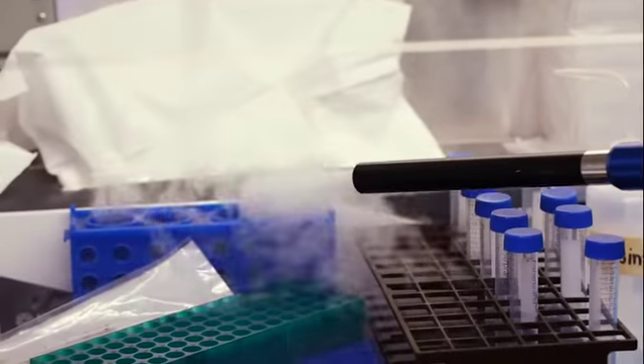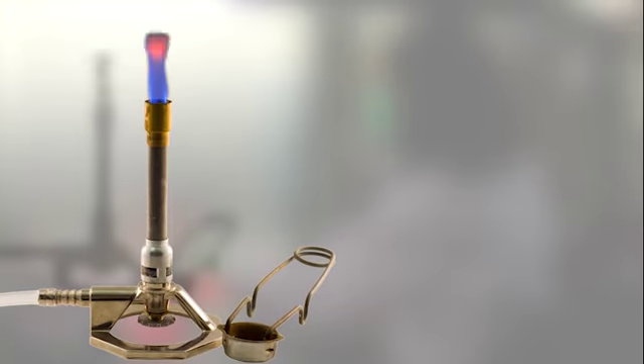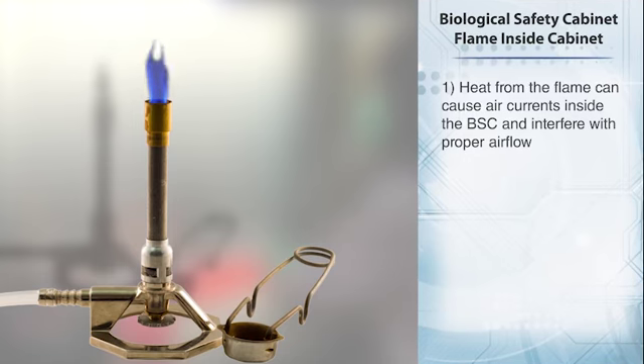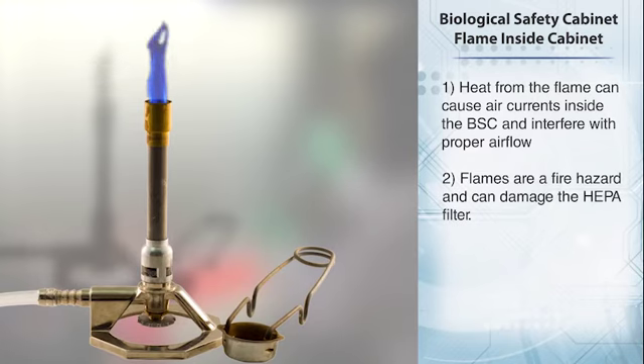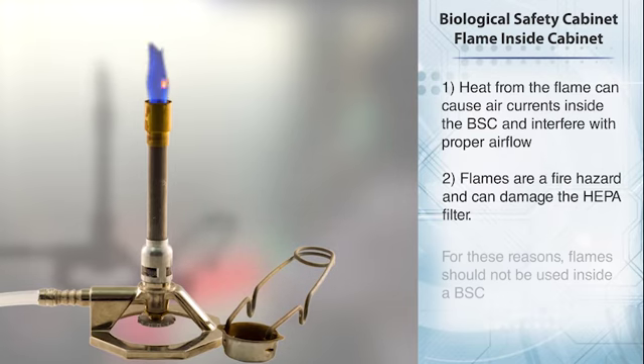One common mistake is overloading the inside of the BSC with too much equipment and/or supplies, or covering the front or rear grills. Another way to disrupt airflow is by using a flame inside the cabinet. This is not a good idea for two reasons. One, the heat from the flame can cause air currents inside the BSC and interfere with proper airflow. And two, flames are a fire hazard and can damage the HEPA filter. For these reasons, flames should not be used inside a BSC.